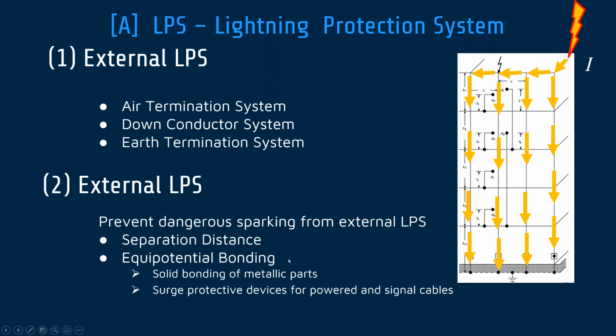Now, equipotential bonding is a simpler thing. You bond all the metal bits together. That's the idea. Bond everything together. So then this threat of voltage becomes nullified. If you have the same voltage on point A to point B, it means you have 0 volt drop between the 2 points and there's no current that can flow. You're safe. Equipotential bonding.